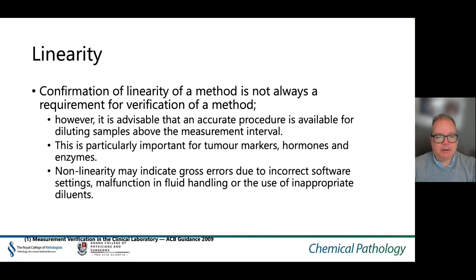Non-linearity may indicate gross errors due to incorrect software settings, a malfunction in the liquid handling system, or the use of inappropriate diluents.